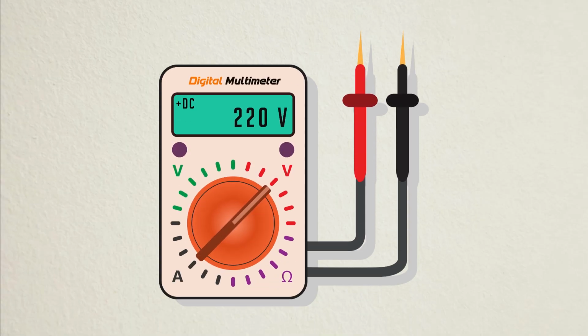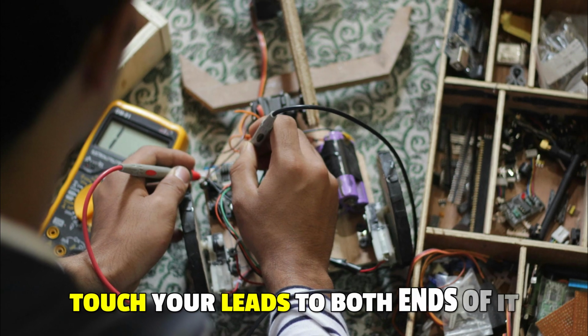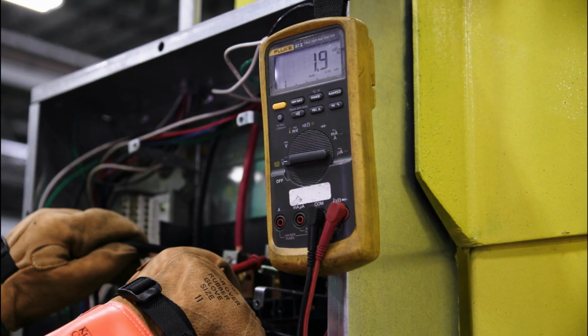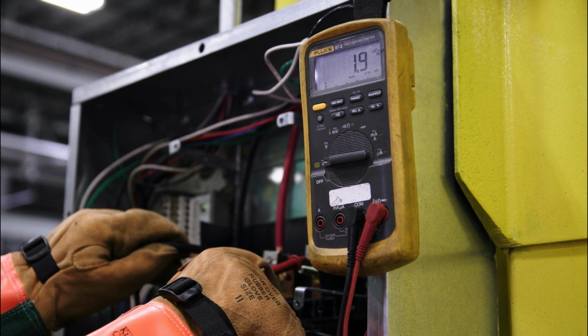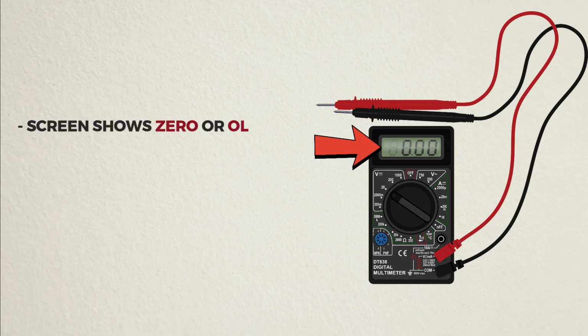If everything looks fine visually, you'll want to grab your multimeter. Then, disconnect the sensor and touch your leads to both ends of it. If you see a steady reading in the kilo-ohm range, the sensor is fine. But if the screen shows 0 or OL, the sensor needs to be replaced.